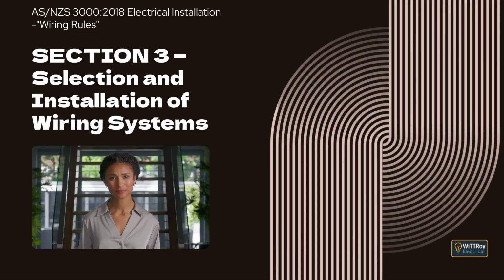Clause 3.3.2.9 Flora. This clause states that where plant growth is likely to create a hazard, the wiring system must be selected accordingly or special protective measures must be used. Clause 3.3.2.10 Fauna. This clause means that where animals are likely to create a hazard, the wiring system must be selected accordingly or protected by special measures.